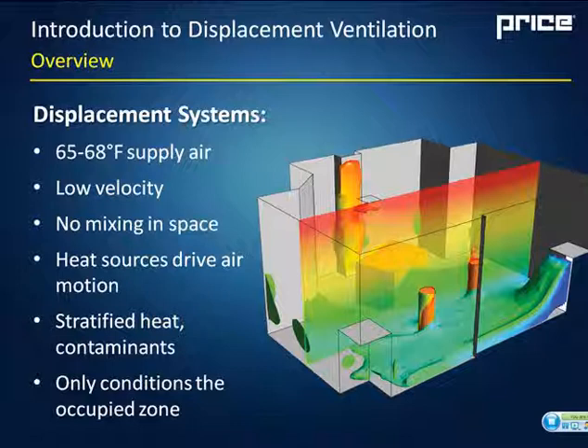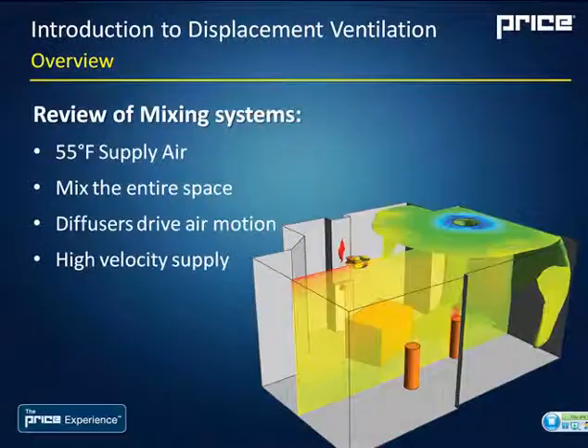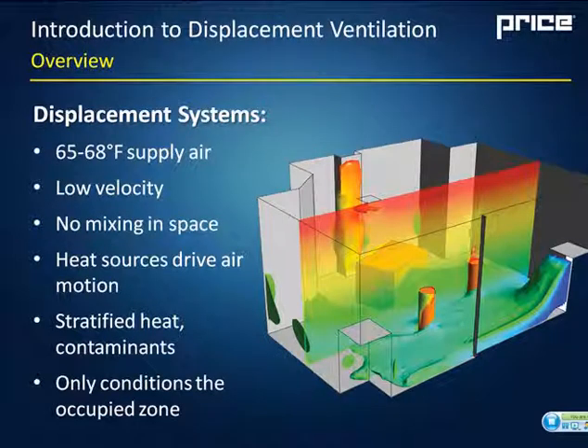So we're just trickling air into the room, and we're allowing the warm heat sources to pull the cool air towards them. Now the significant difference here, aside from the velocity, is that we're stratifying all of the heat and the contaminants at the ceiling level. You'll notice that there's a much different temperature pattern in the room. Whereas we saw with this room where the temperature or the color is pretty much even across the room, in the displacement system we're seeing a dark red near the ceiling, which is indicating return temperatures up into the 80 degrees.